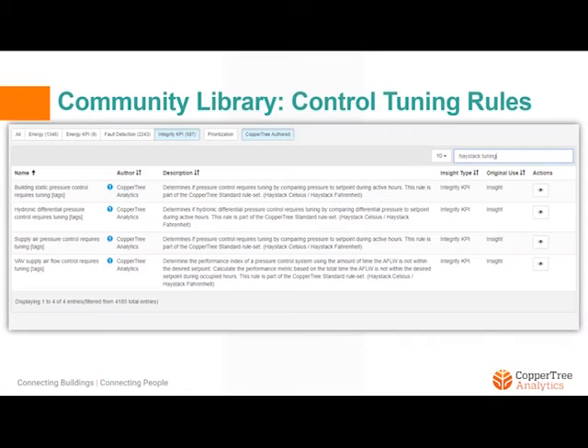Again, within the community library, as commissioning professionals, you may be very interested in control tuning rules. Well, you can search for tuning. In this case, on the top left, you can see that integrity key performance indicator rule category has been highlighted. So just within that category, there are 4 different rule templates that are available. Building static pressure control requires tuning. Hydronic differential pressure control requires tuning, so that can be applied on hot water systems and chilled water systems. Supply air pressure and VAV supply airflow control related rules.